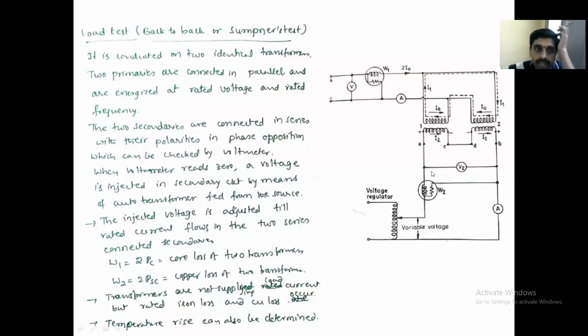The test is conducted on 2 identical transformers, and the 2 secondaries are connected in series with their polarities in phase opposition. As I said, if they are not in phase opposition, there will be a circulating current. So we have to check first whether they are in phase opposition or not. Once the voltmeter reads 0 value, there is no voltage and no circulating current here, which means they are in phase opposition. Then only we go ahead with the test.